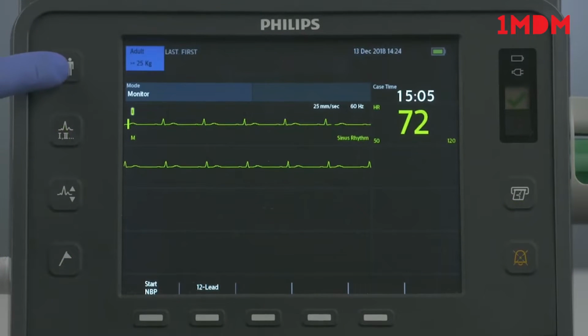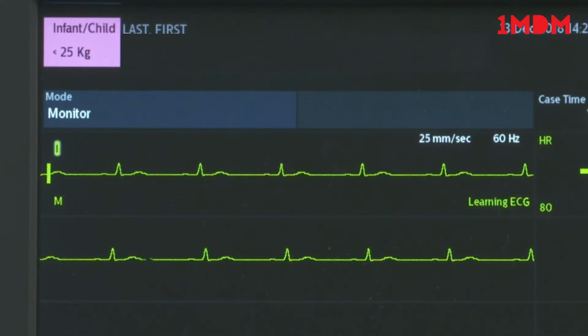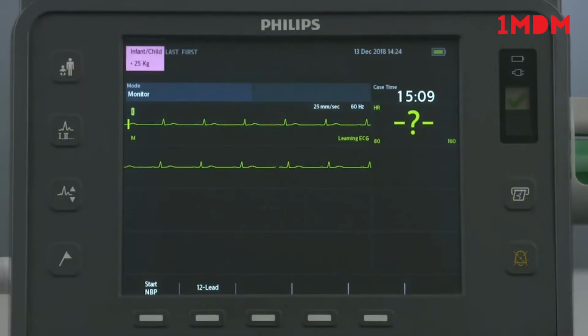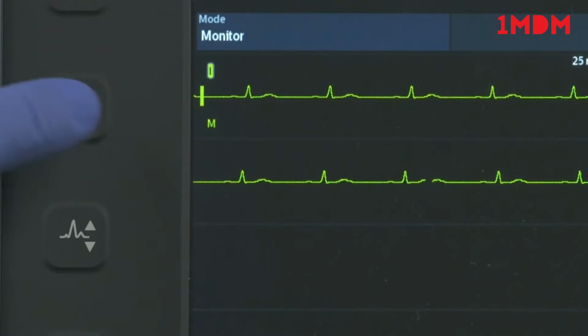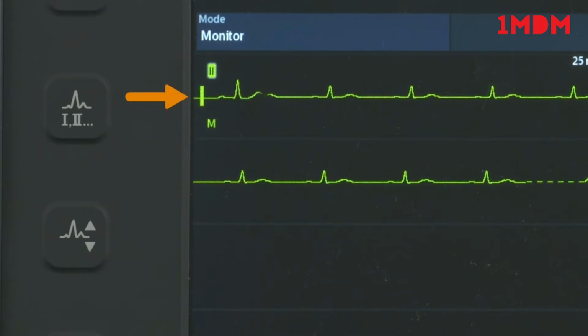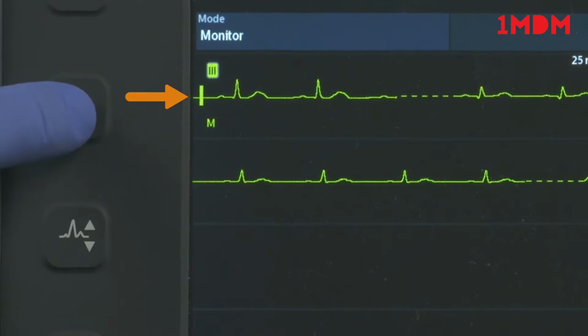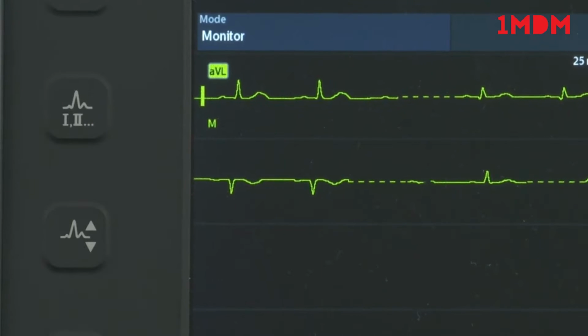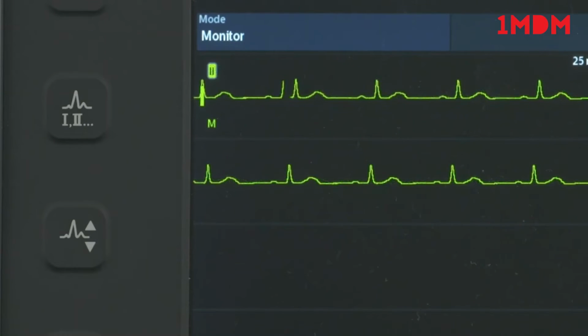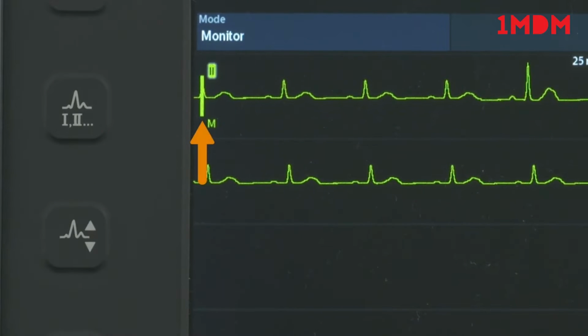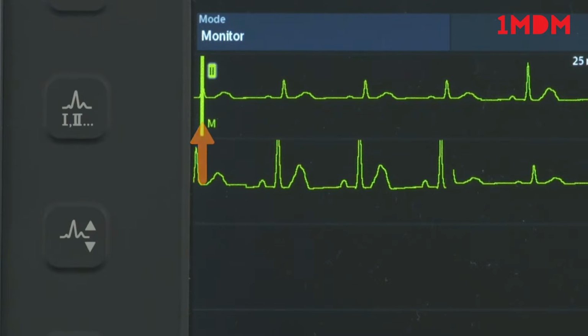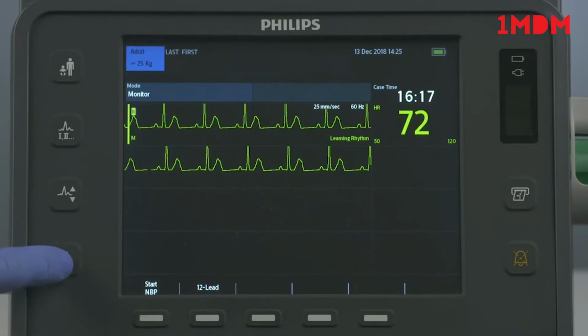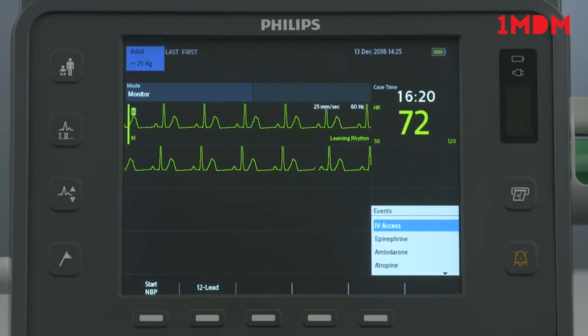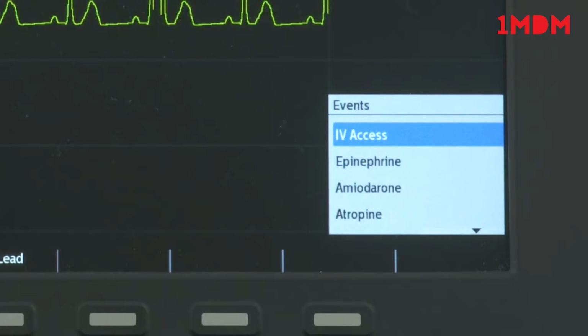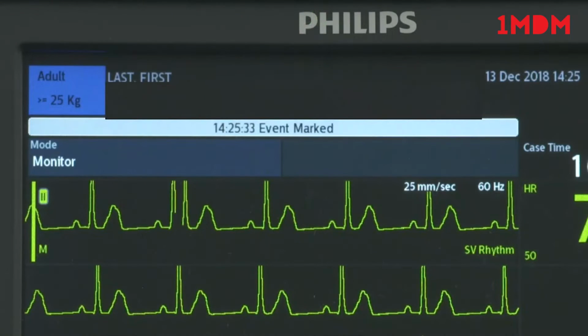The Patient Category button switches between adult and child patient categories, changes alarm limits to the new patient category, and adjusts the energy setting for defibrillation in AED mode. The Lead Select button changes the ECG lead in Wave Sector 1, cycling through the available ECG waves and changing the displayed wave and its label. The ECG Gain button increases the ECG waveform vertical scale of the primary lead by 1 setting. Press the Mark Event button to insert a time-stamped annotation on the ECG strip and in the Event Summary Report to note events as they occur, including certain drug administration.